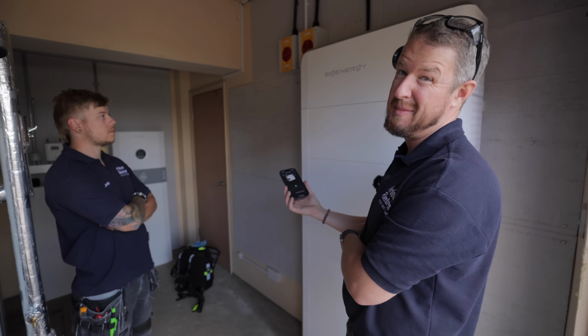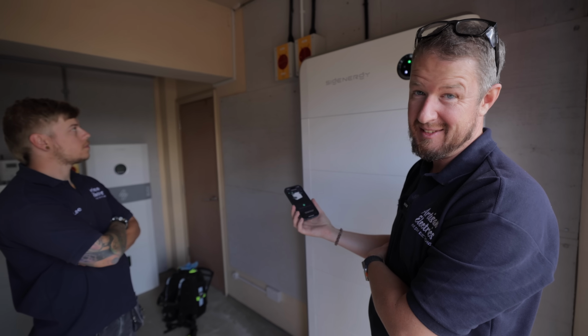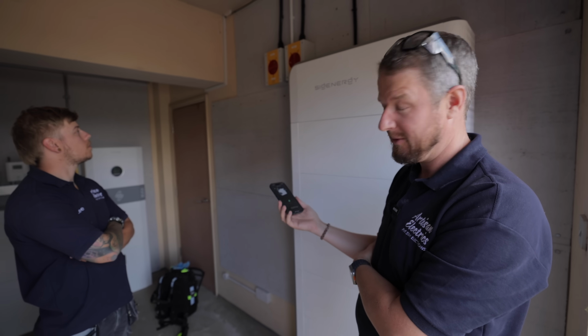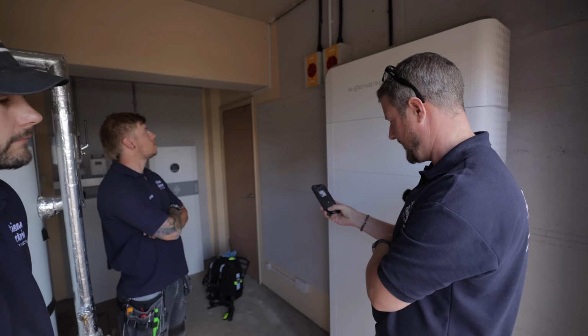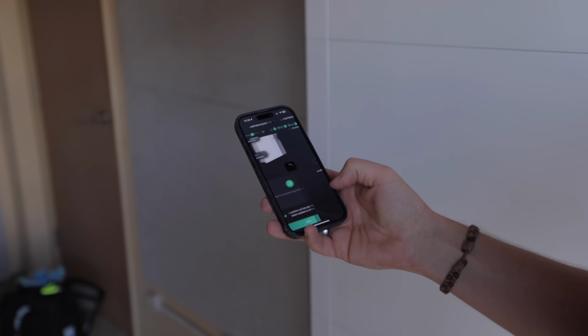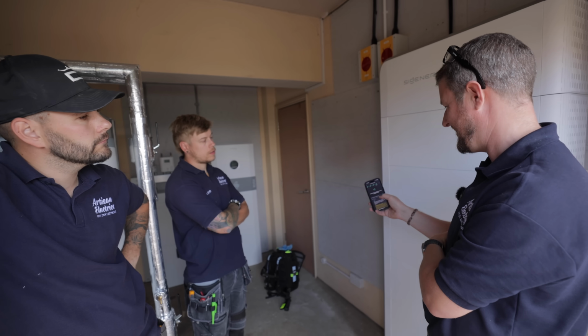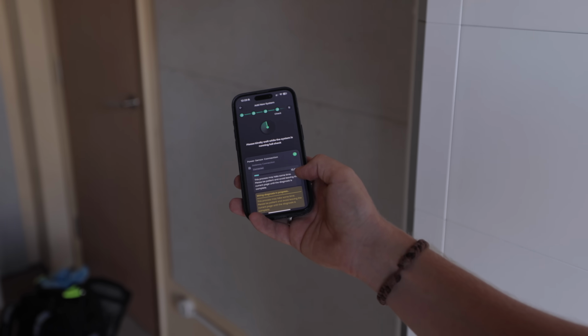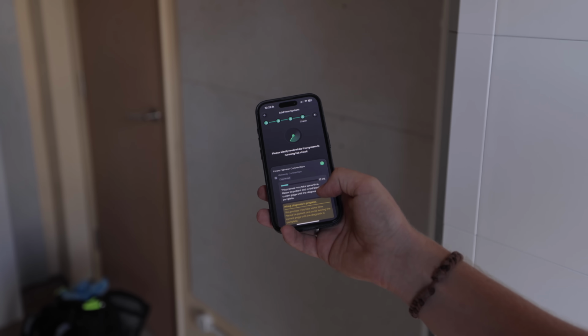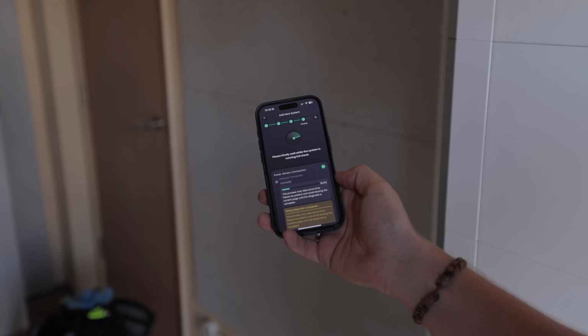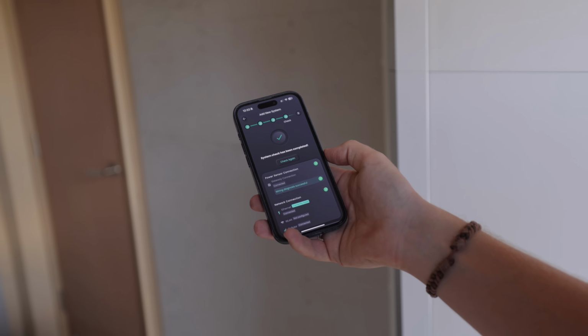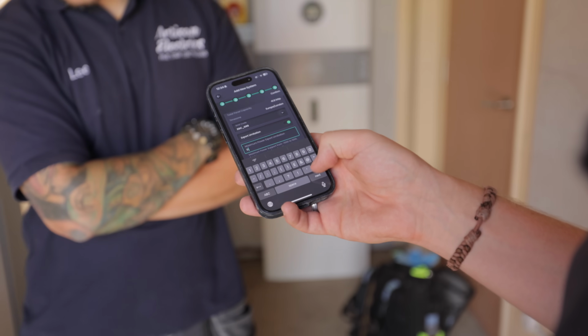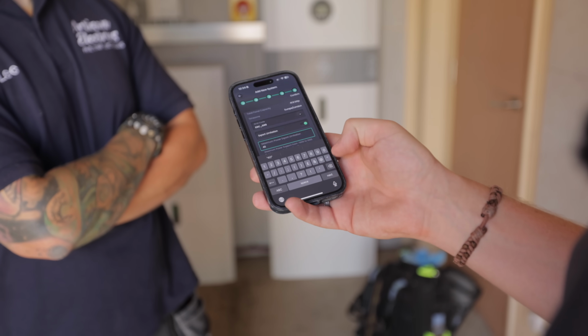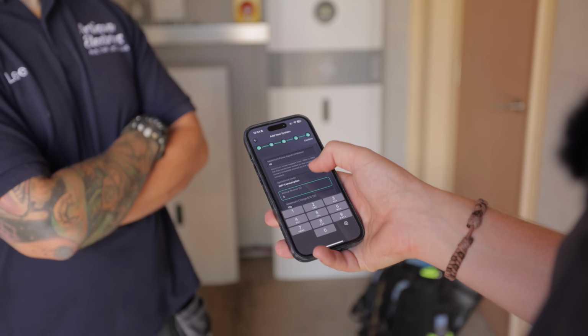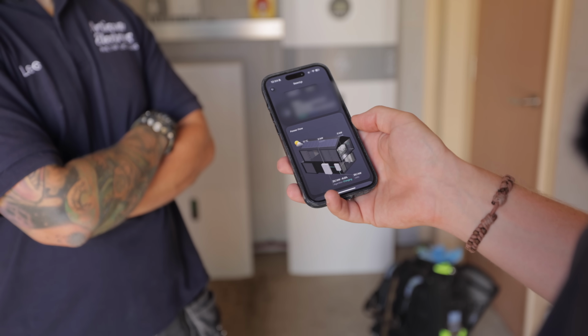So that took about 3 minutes, so longer than the 36 seconds that they said, but still really quick, which is what we love about this system. We're just going to confirm that all the devices have been added. Click next. Okay. Oh, power sensor connection. Look, there we go. So it's basically diagnosing the wiring of the power sensor to figure out what the system's doing. Wiring diagnosis successful. So we're going to put an export limit in here, which the DNO have told us we need to do, which is 40 kilowatt, and then confirm, and that's it.